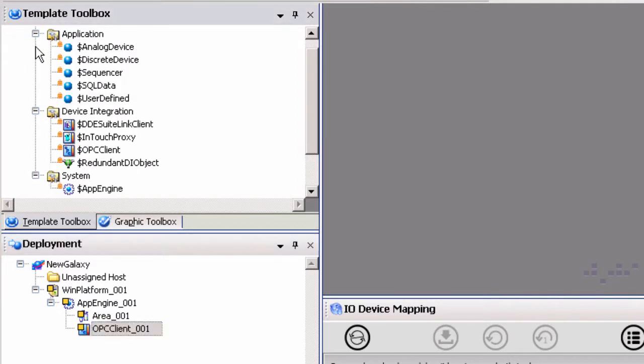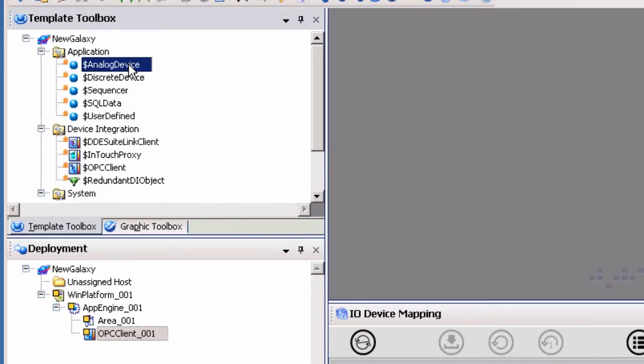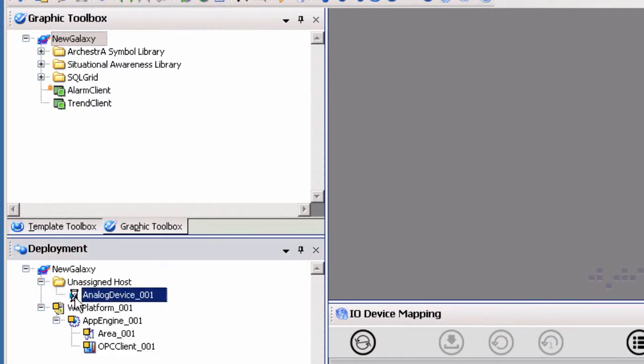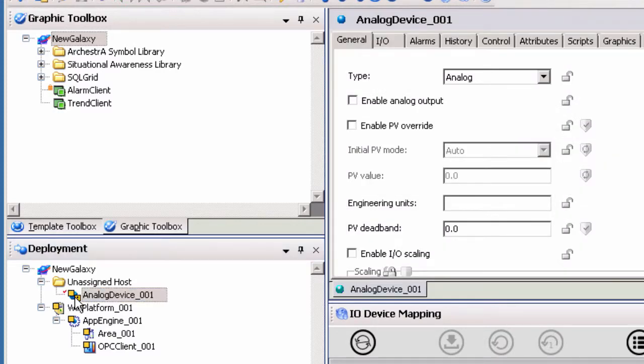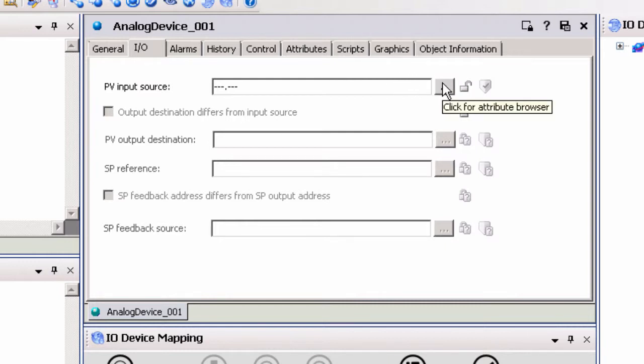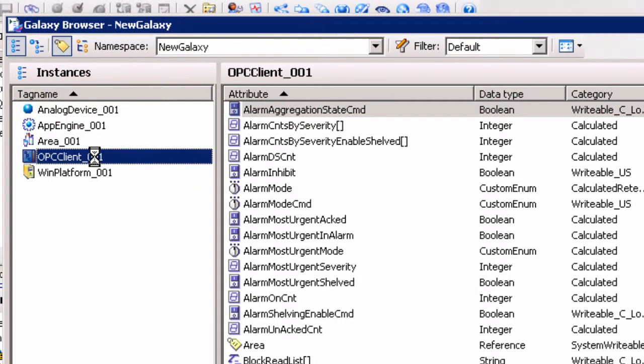In order to make a connection to TopServer, the final object needed is an application object. We will use the Analog Device Application Template object because we will be connecting to a tag in TopServer with an analog data type. For more information on application objects, please reference your Wonderware documentation. Drag and drop the Analog Device Application object under the Unassigned Host folder and double-click the object to open the Properties dialog. An item must be assigned to the object. This assignment is made by entering the full item reference in the PV Input Source field. If you do not know the full item reference, you can click on the ellipses button to launch the Attribute Browser.